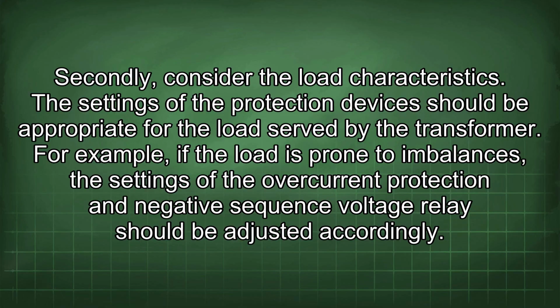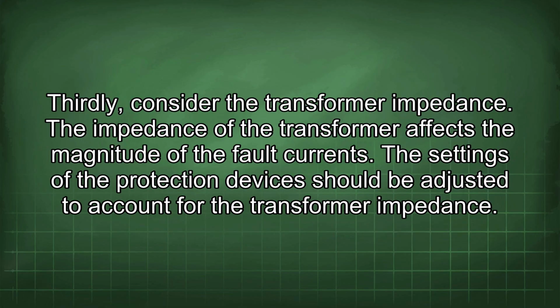For example, if the load is prone to imbalances, the settings of the overcurrent protection and negative sequence voltage relay should be adjusted accordingly. Thirdly, consider the transformer impedance. The impedance of the transformer affects the magnitude of the fault currents. The settings of the protection devices should be adjusted to account for the transformer impedance.